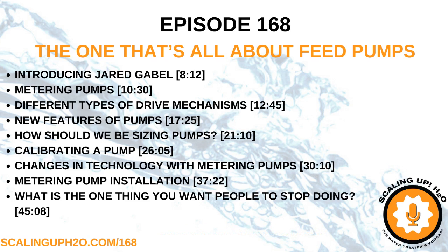So there are different ways to actuate the pump. Whether it's a piston, a peristaltic, or a diaphragm will have certain benefits in that chemistry that's being injected, or in the physical setup of the suction conditions, whether it's flooded suction or a suction lift. Another consideration is materials of construction. And when you order these pumps, you can order them with a multitude of different heads. How do you know which material to choose for the application that you're using?